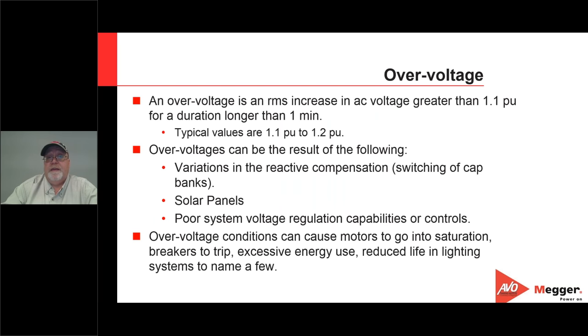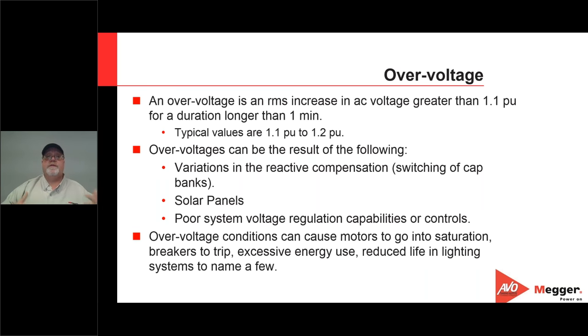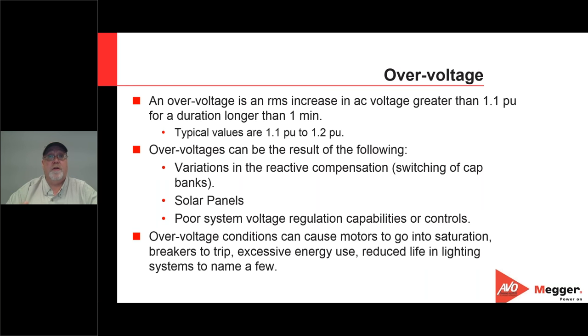An over voltage is an RMS increase in AC voltage greater than 1.1 per-unit, or 110% of the average RMS, lasting longer than one minute. Typical values can be 110% to 120%. Over voltages can result from reactive compensation such as switching in capacitor banks, solar cells — a common cause in residential and small commercial facilities — as well as poor system voltage regulation.